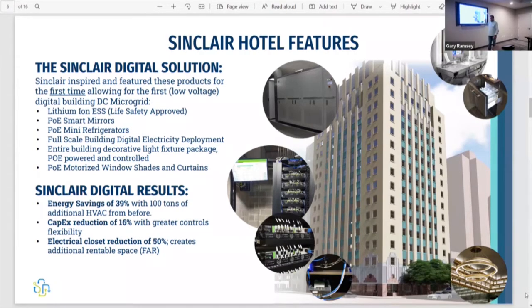So this is where it got very interesting. Sinclair has 12 guest rooms per floor. So, conventional wisdom, we pulled 12 18/2 cables in, and two extra, one for the hallway and one extra pair. We had an issue. It rained during construction and moisture got into our conduit, and the cable was indoor rated cable. But I learned another thing: in future, spend 15-20% extra and buy an indoor/outdoor rated jacket, so that it will resist moisture. So when we replaced it, imagine 16 stories, 14 cables per floor. Can you imagine the bundle size?